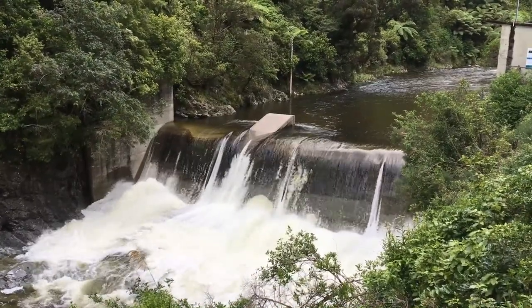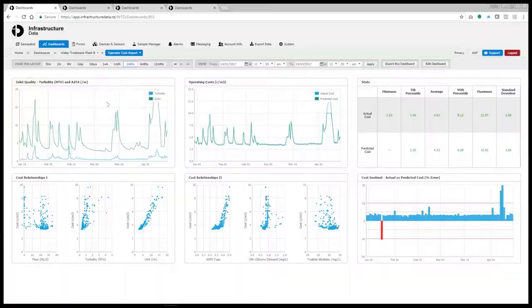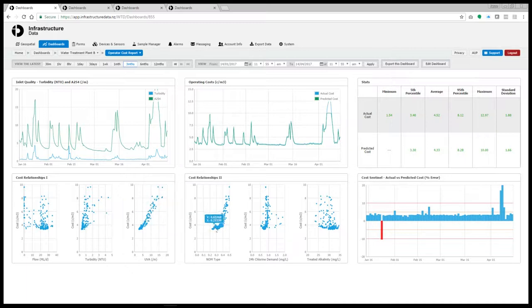Now that we've explained how online treatment costs for a source like this can be calculated, we'll show a few examples of how that can be used in infrastructure data to provide operational and management insight. From an operations perspective, this dashboard shows the inlet water quality and the actual and predicted cost to treat. As would be expected, the cost to produce water increases when the raw water quality deteriorates. However, it's not immediately obvious what is driving the cost increase. We can drill into the data and plot costs against all sorts of variables to determine what has the most impact on operational cost. In this example, it's the amount of dissolved organics and in particular the type of dissolved organics present which is really impacting operating cost. This is a great way to increase operator understanding of the process and allow them to fully grasp the impacts of increasing chemical doses.